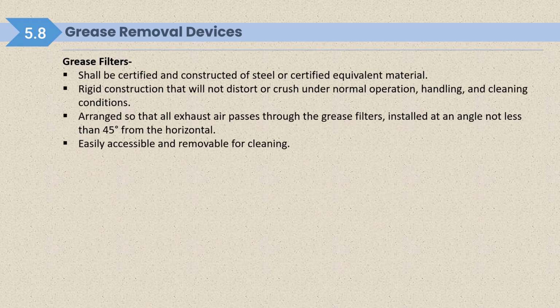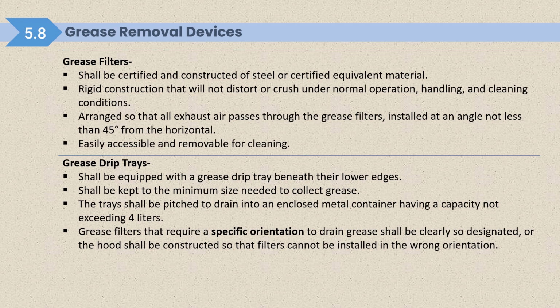Grease filters shall be certified and constructed of steel or certified equivalent material. Rigid construction that will not distort or crush under normal operation, handling and cleaning conditions. Arranged so that all exhaust air passes through the grease filters. Installed at an angle not less than 45 degrees from the horizontal. So you will see the grease filters, they are always installed at an angle, but it should not be less than 45 degrees. Easily accessible and removable for cleaning. Grease filters shall be equipped with a grease drip tray beneath their lower edge. So near the filter you will see that there is a tray type of structure.